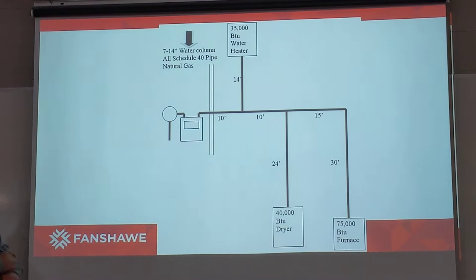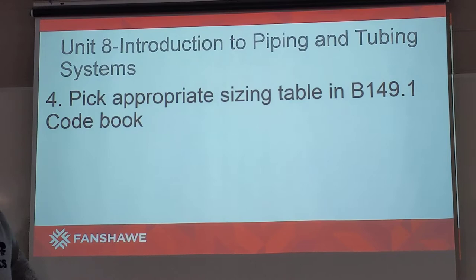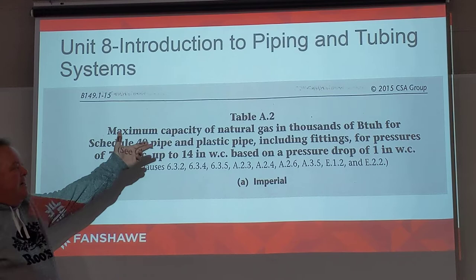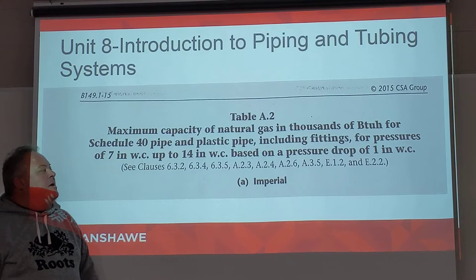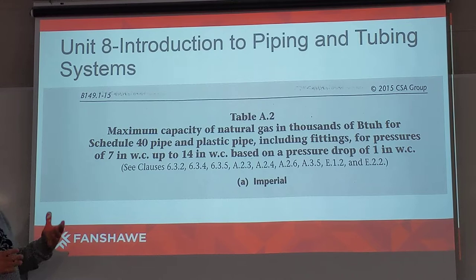Back to our diagram, you can see a block arrow showing all the information needed to pick our table. The next step is picking the appropriate table in the B149.1 code book. The table we come up with is Table A2. Reading through that header: the maximum capacity of natural gas in thousands of BTUs per hour for schedule 40 pipe and plastic pipe, including fittings, for pressures of 7 inches up to 14 inches water column, based on a pressure drop of 1 inch water column. A lot of students have problems picking the right table — make sure you're on the correct one. There's nothing worse than doing the whole piping example perfectly but using the wrong table, because you'll get the wrong answers and no marks.